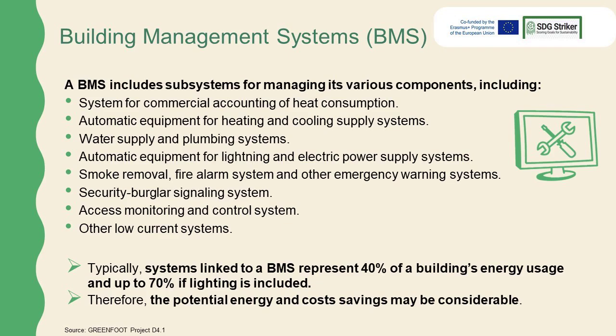A BMS includes subsystems for managing its various components, including system for commercial accounting of heat consumption, automatic equipment for heating and cooling supply systems, water supply and plumbing systems, automatic equipment for lighting and electric power supply systems, smoke removal, fire alarm system and other emergency warning systems, security burglar signaling system, access monitoring and control system, other low current systems. Typically, systems linked to a BMS represent 40% of a building's energy usage and up to 70% if lighting is included. Therefore, the potential energy and cost savings may be considerable.